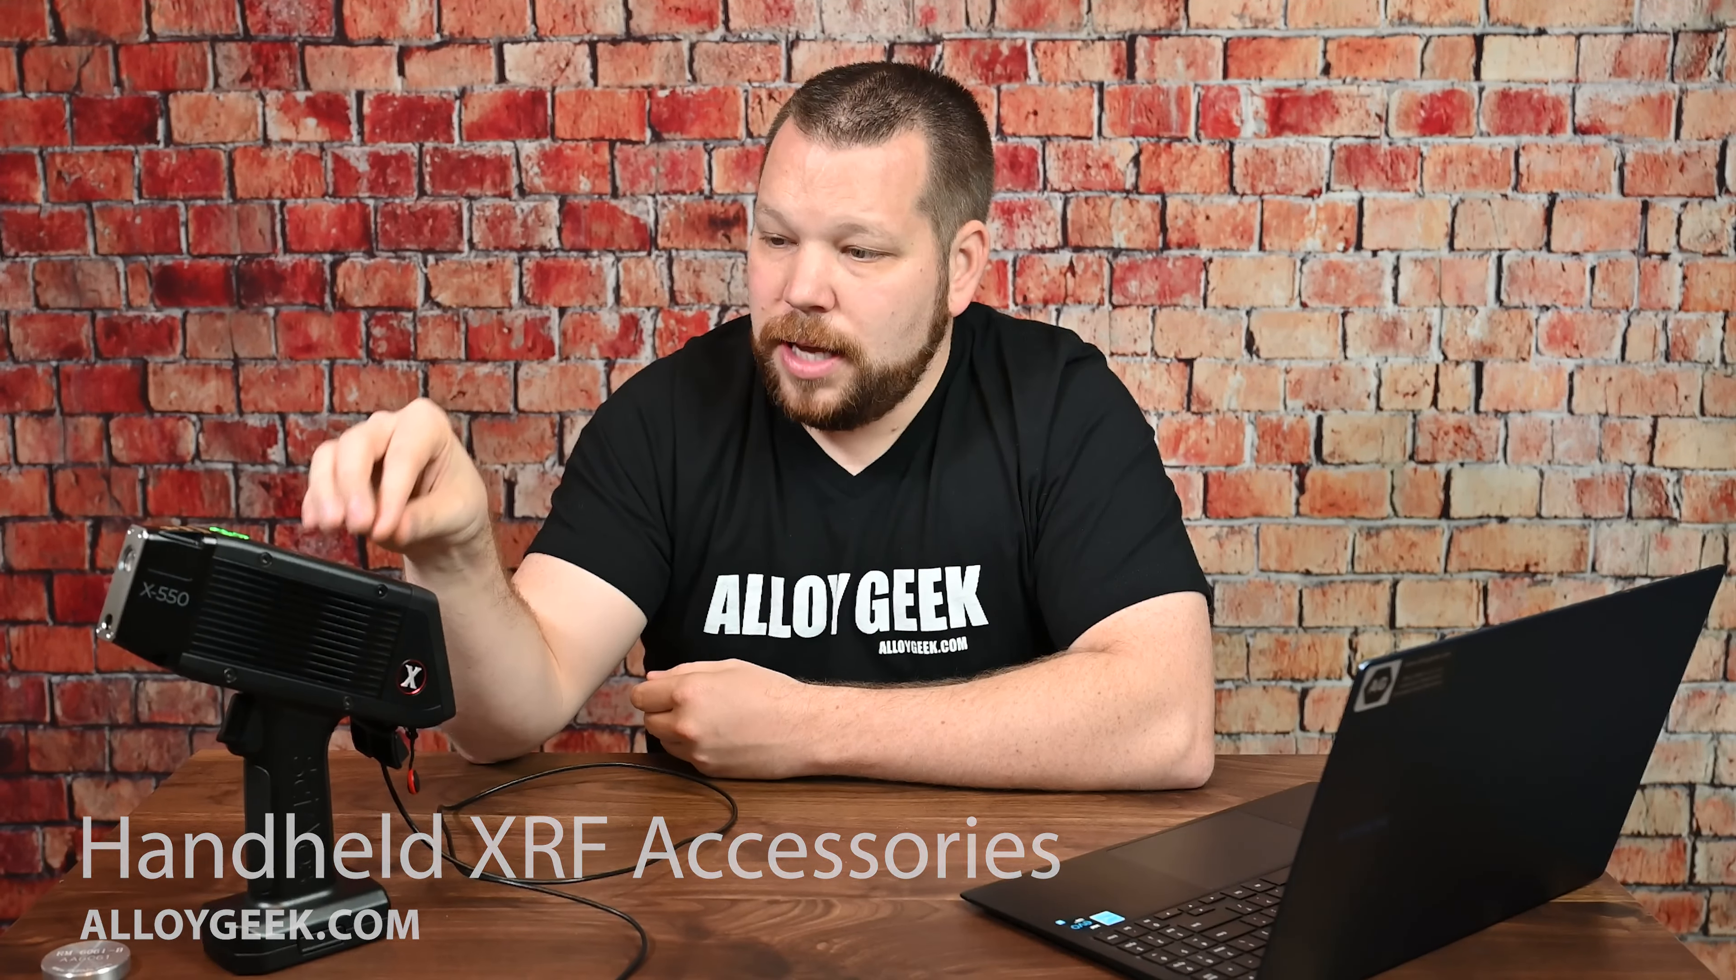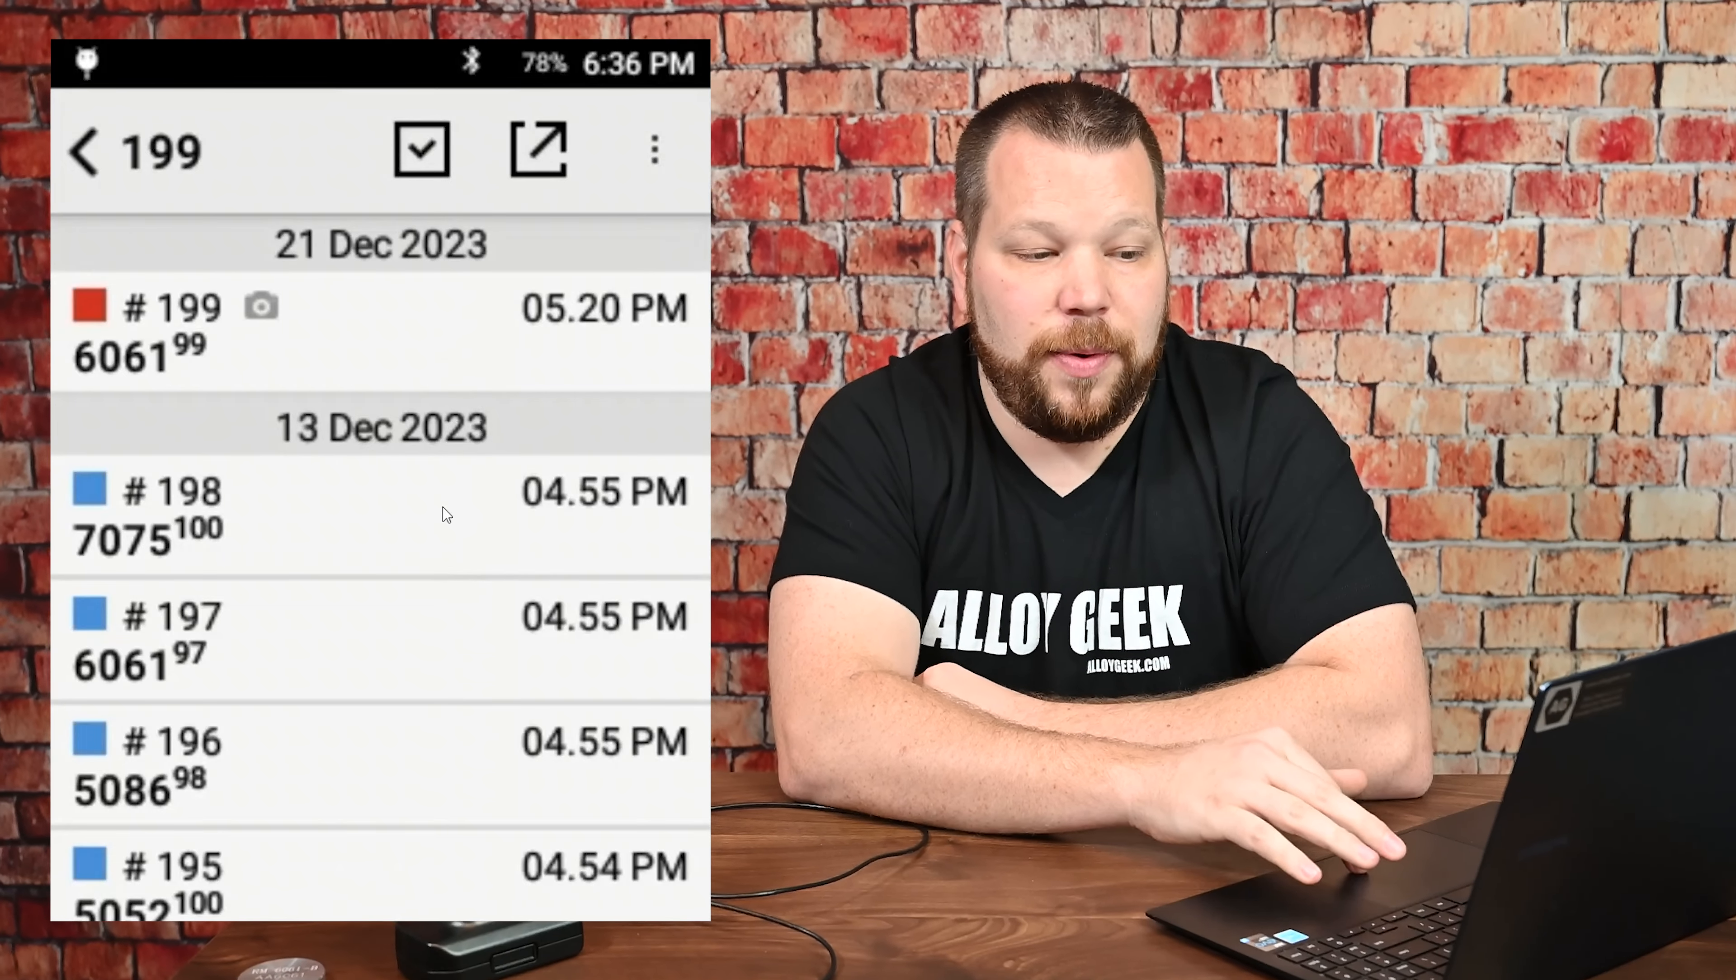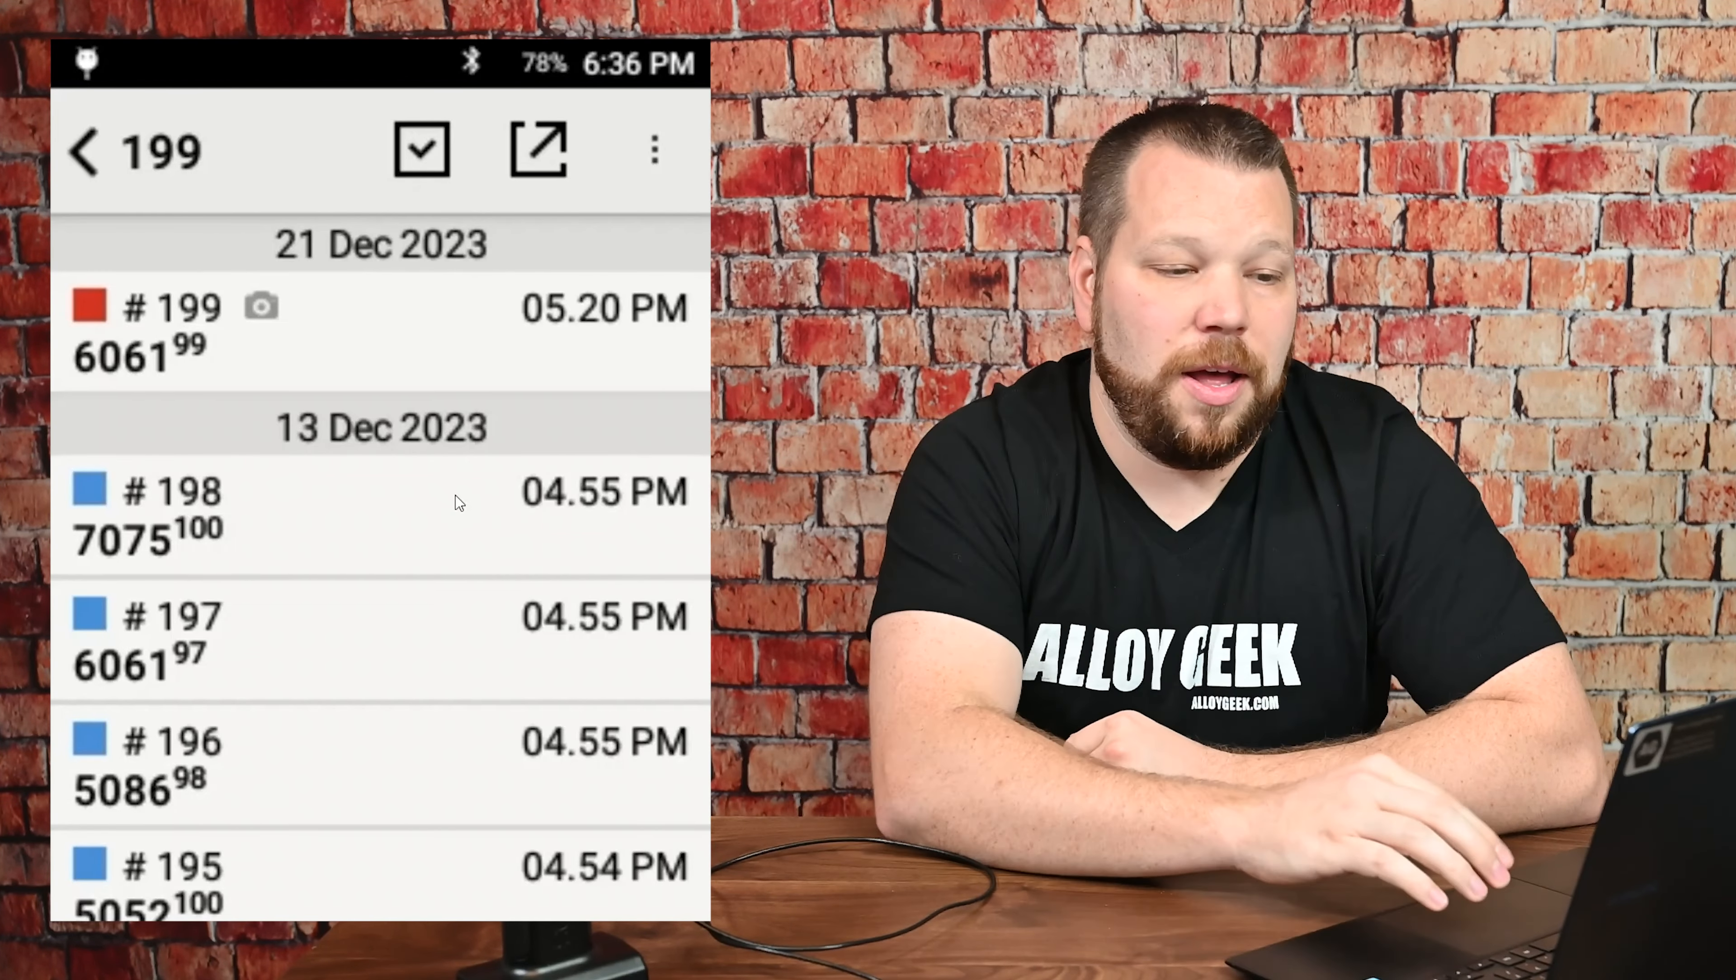So then you're going to take the data on your analyzer and export that to an SD card. So I'll show you how to do that. The first thing you're going to do is you're going to go into the results mode. So you're going to click on results and you can see we have all these different results here. Now, if you have a lot of results or you're trying to filter by specific date ranges and take specific results off, I'll show you how to do that too.